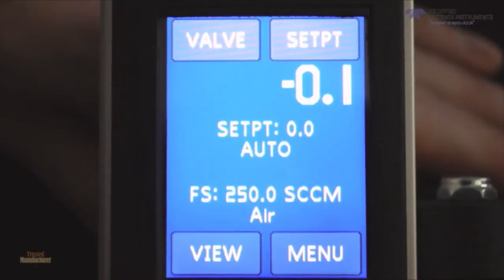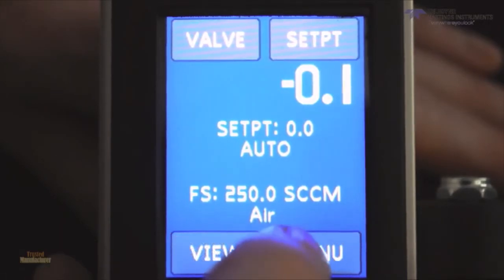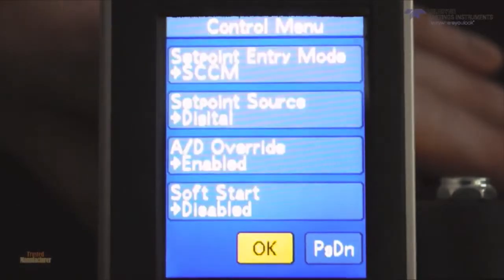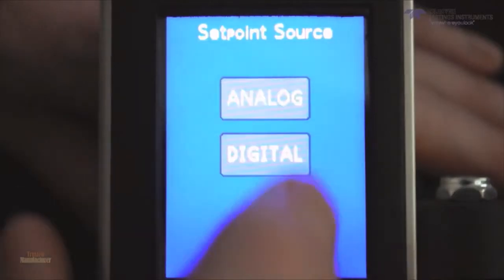Alright, the other thing I've got to do is to select how I'm going to enter the command signal. Right now the unit is set up in the digital command mode, which means that if I enter a command on the front panel, it'll respond if I send a command via RS-232, 485, or USB. So I want to take it from the digital command mode into an analog command mode. To do that, I go here, Menu, Flow Control, and I'm going to make the set point source now analog.